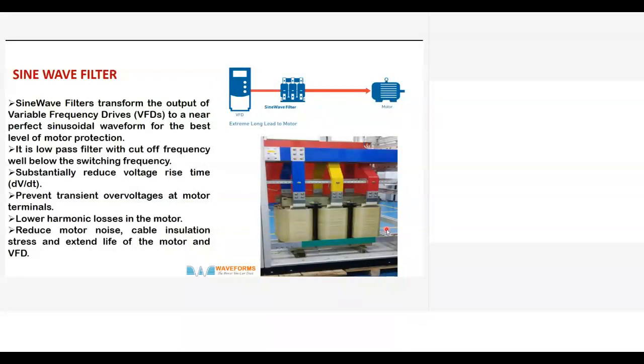So this is a 1450 ampere filter which we installed for multiple drives driving a single motor of 900 kilowatts. We have installed this 1450 LC filter, or we call it a sine wave filter, and they were having issues like motor burning and failures. Once they installed it, they were quite satisfied. They placed an order for the second one.